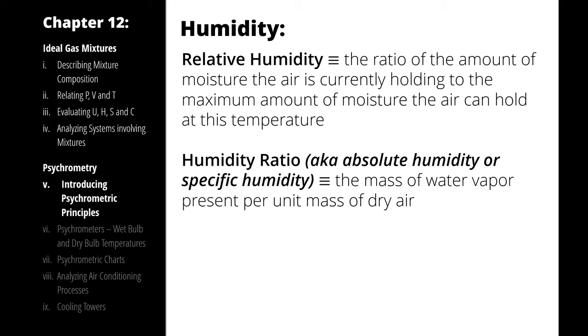The percentage expressed by relative humidity is the amount of water currently in the air divided by how much water the air can hold. So if the relative humidity outside is 55%, the air is currently holding 55% of its capacity to hold water. Humidity ratio is a raw proportion — it is mass of water vapor per unit mass of dry air. Generally, relative humidity is more useful when describing human comfort, and humidity ratio is more useful for engineering calculations.